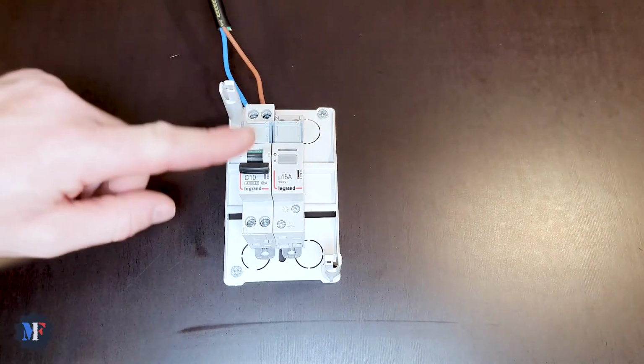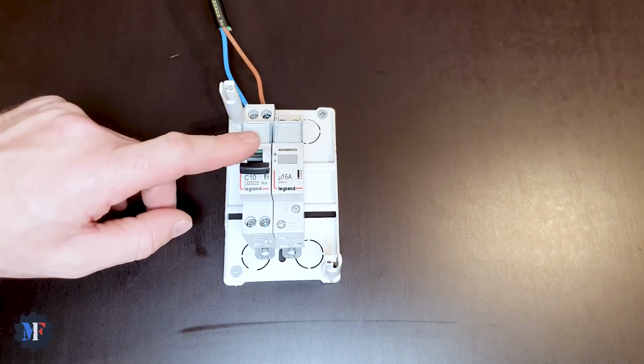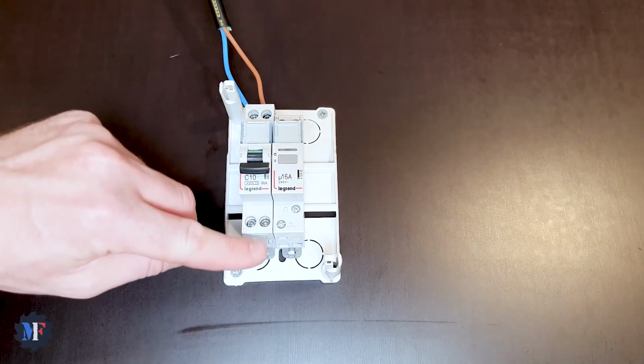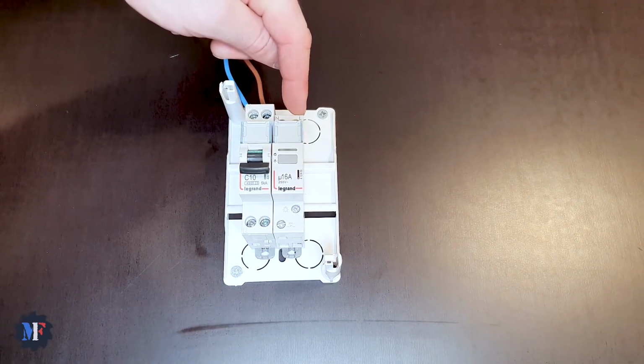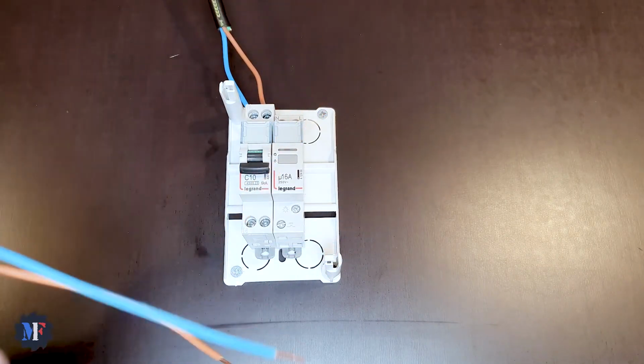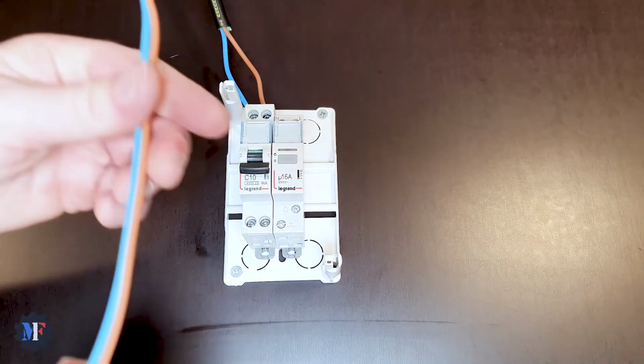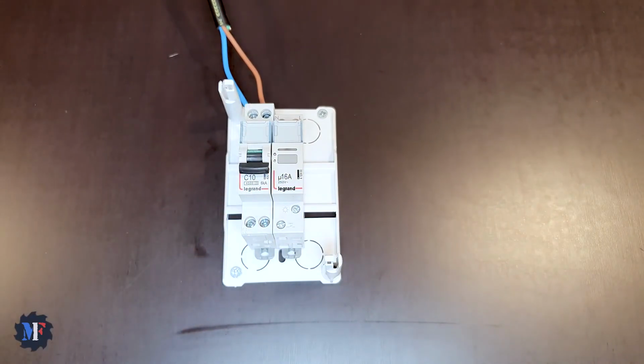So now the idea is to connect the latching relay to the circuit breaker. Neutral, hot, there we go, and we connect neutral and hot at the top. The wire is here, it's prepared, it's 2 conductor, 2.5 square millimeter cable. I plug it in and then we'll take care of the push buttons.